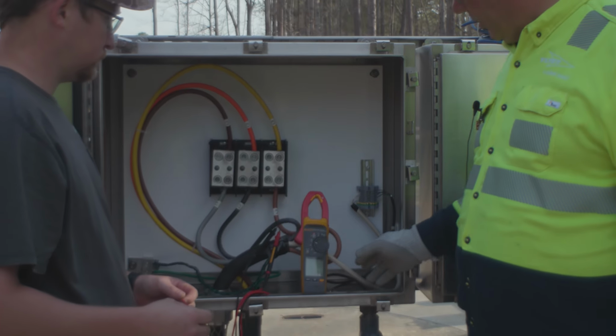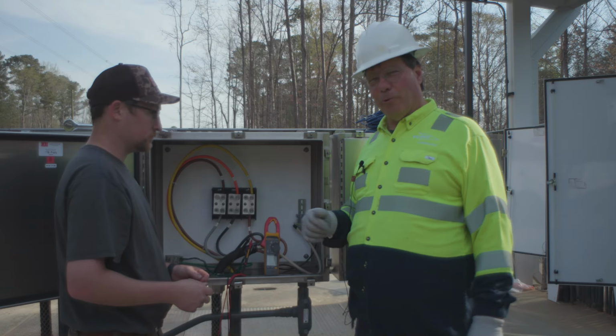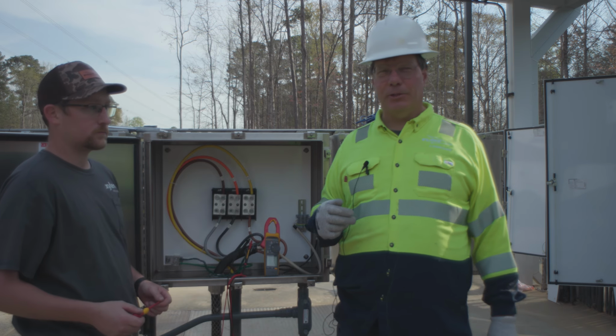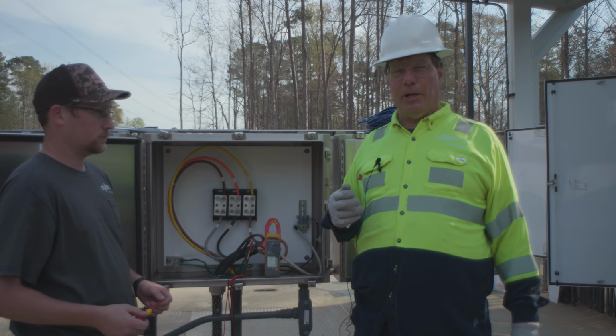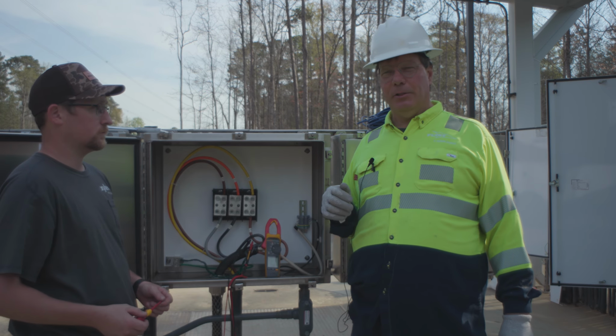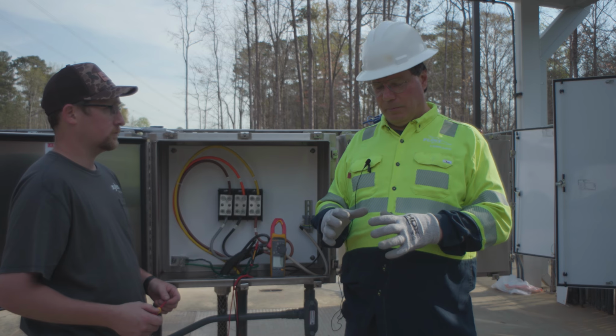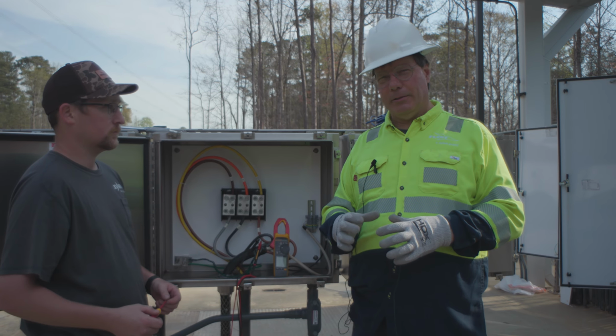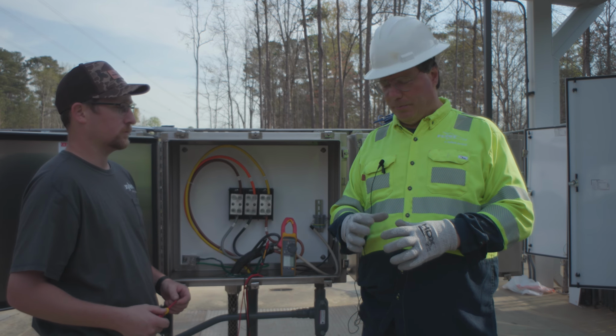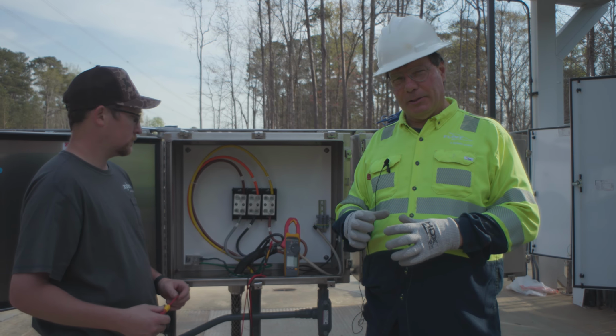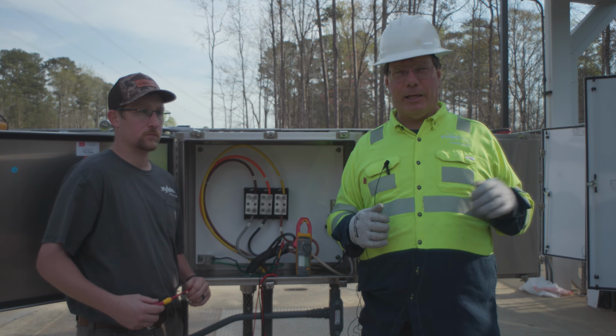All right, in addition to the motor power leads, there's also a control lead. The control lead has 4 wires in it. 2 wires are used for the thermals, and the other wires are used for communication to a pump sensor monitoring device that's in the top of the pump, in that terminal box in the pump. It's called the pump electronic module, and it talks digital communication over wires 1 and 2 to the base unit that's inside the control panel. And we'll go over that in a little bit.